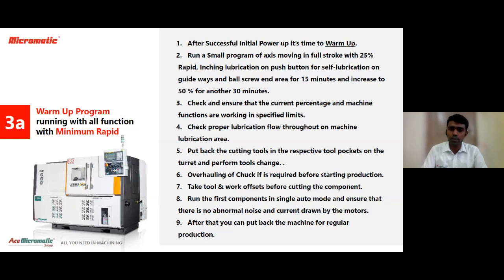You cross check how much the load is at the start time, and also run it for 15 minutes at 25% load itself, and cross check the load once again. If everything is through, you again increase the rapid to 50%, then run it for another 30 minutes. So these are the conditions. During this cycle, please cross verify whether all the required areas have been lubricated or not. So you have to cross check the guideways and ball screws. These are the important areas which should get lubricated.